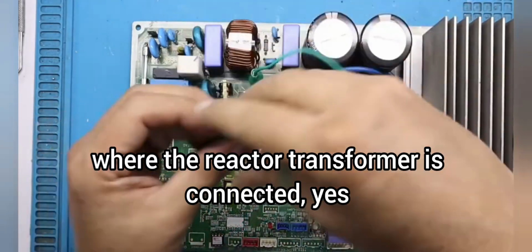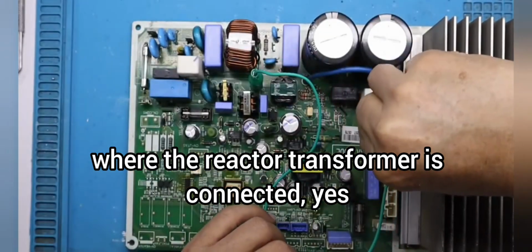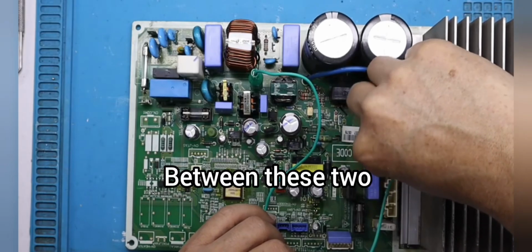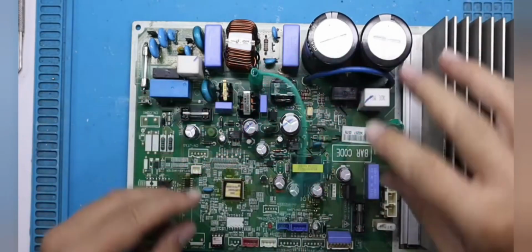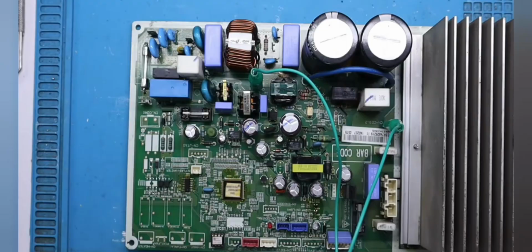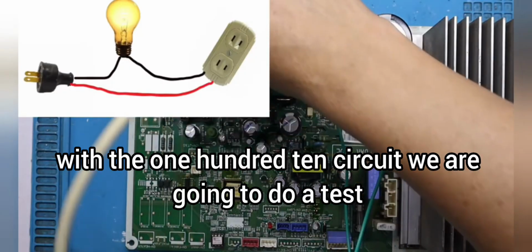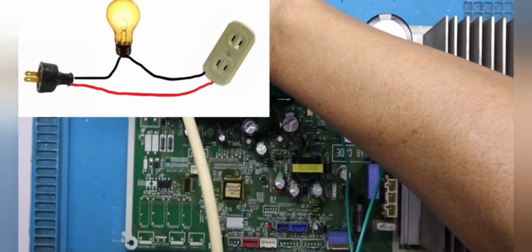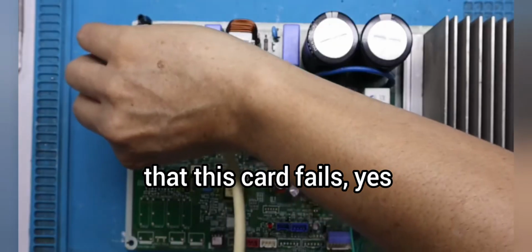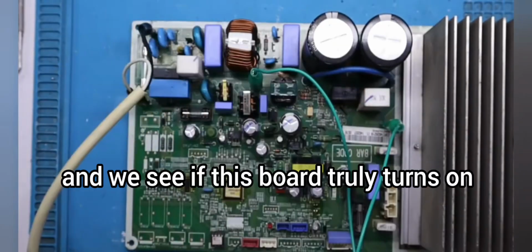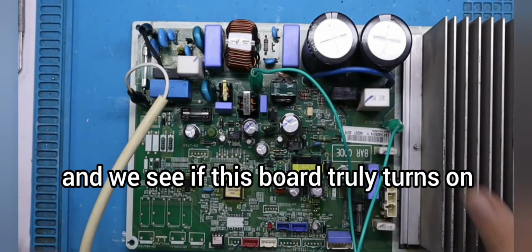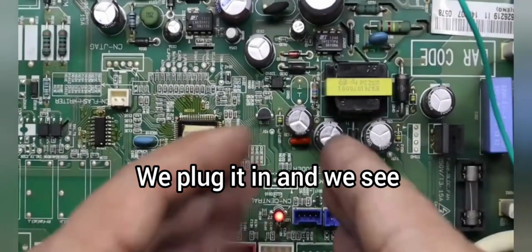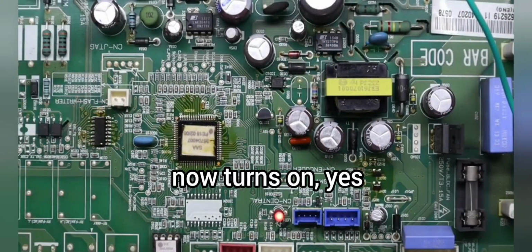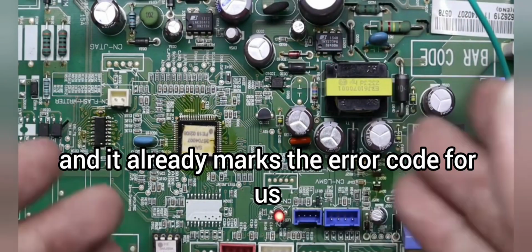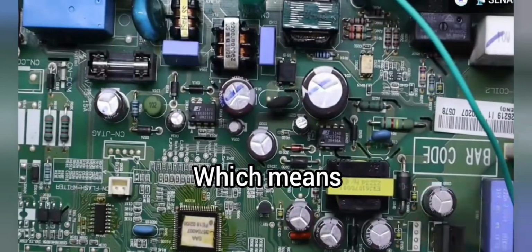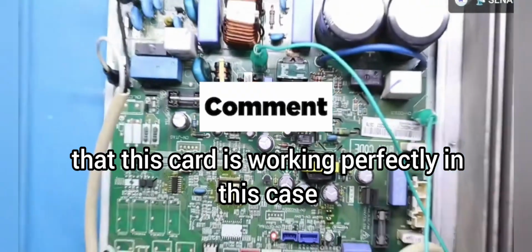We make a bridge where the reactor transformer is connected, between these two. Well now, with the 110 circuit we are going to do a test to protect it in case this card fails. If we do the test, we see if this board truly turns on. We plug it in and we see that the board now turns on. There the LED can be seen and it already marks the error code for us, which means that this card is working perfectly in this case.